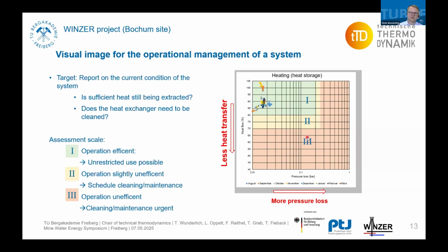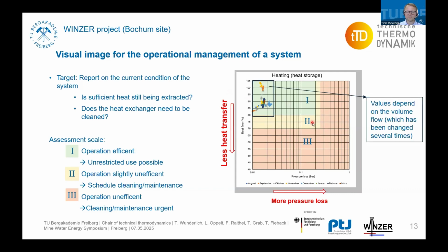That's why we have got more like a traffic light system there, from green to red. If we've got the heat flow compared to the pressure loss, then we can estimate whether our heat exchanger should be cleaned. This one is the test series from Bochum - the value depends on the volume flows, that's why it's in this green area.